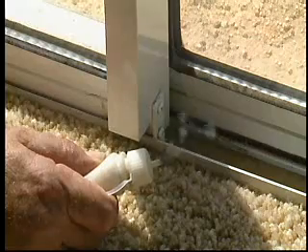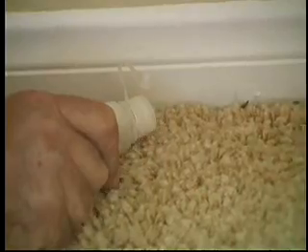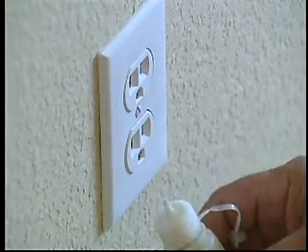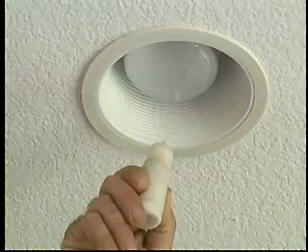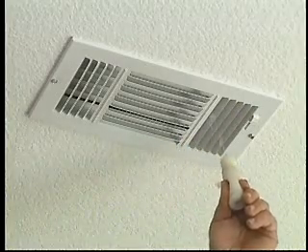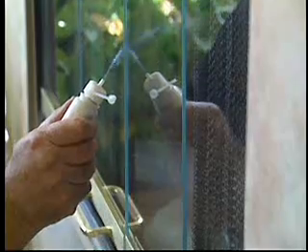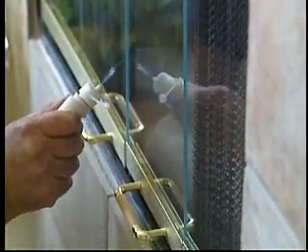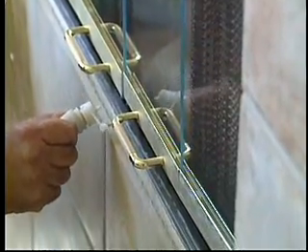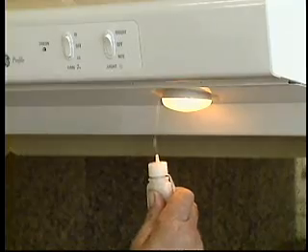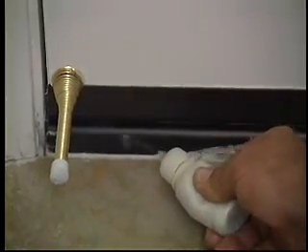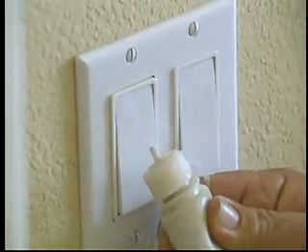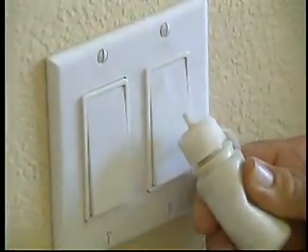The leakage sites are typically around the windows, around the doors, bottom plates, receptacles. A big one is ceiling lights. Ceiling lights leak a great deal. Dampers, duct systems. A huge one usually is fireplaces. The dampers are either messed up or there are a lot of places around the fireplaces themselves that leak a great deal of air. But with the visible smoke, when the house is pressurized and the air is blowing into it, we can pinpoint exactly where all the leaks are and correct them. Oh, fascinating. Thank you, Scott.